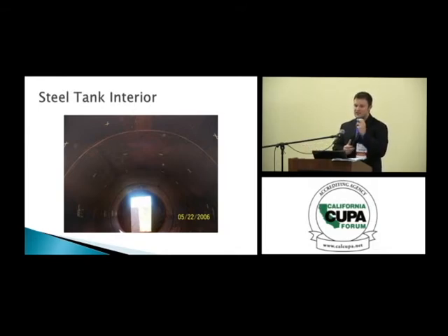People look at confined space and go, 'oh yeah, it's just a hole in the ground.' But that's confined space. You need to monitor air quality not just at the entry point but at different stages throughout the depth. If any of you are considering taking confined space training, it always makes you more effective — and especially if you ever get the opportunity to go inside of a tank.